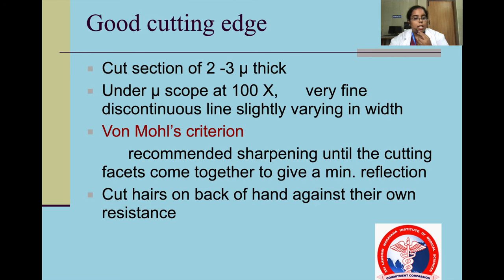A good cutting edge cuts sections of 2 to 3 microns under microscope at 100x, showing a very fine discontinuous line slightly varying in width. Von Mohl's criterion recommends sharpening until the cutting facets come together to give a minimum reflection; a check is to cut hairs on the back of the hand against their own resistance.